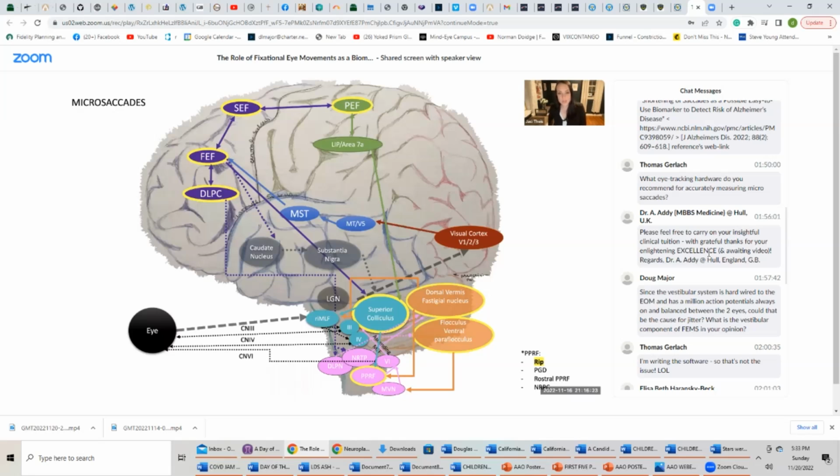So what speed of an eye tracker will be sensitive to fixational eye movements? As of right now, I would say it would have to be about 400 Hertz because we think that fixational eye movements are about 150 to 200 Hertz. So you want to double that according to the Nyquist theory. So you're looking for something that's, I would say, 400 Hertz. I think you're going to be safe based off of that theory, and that's to be able to detect the properties of microsaccades.